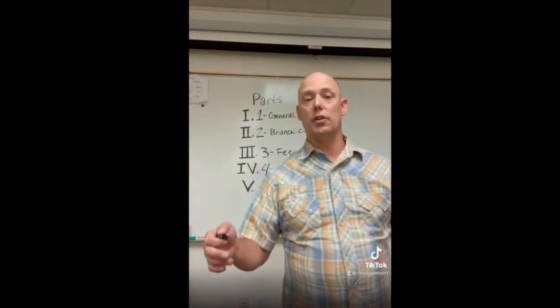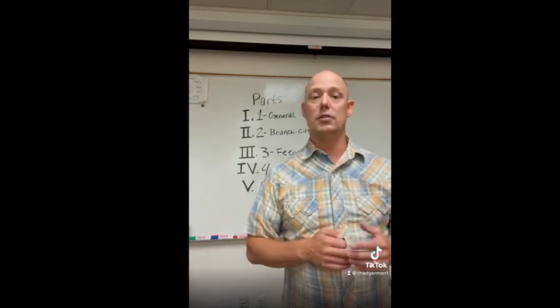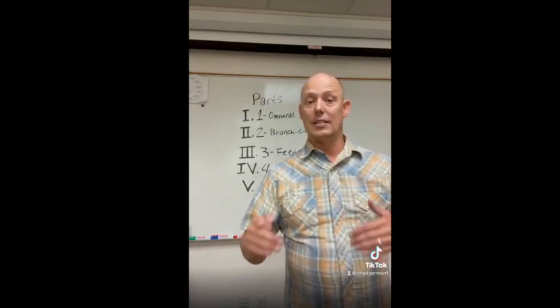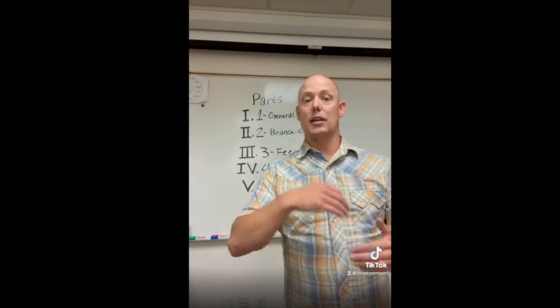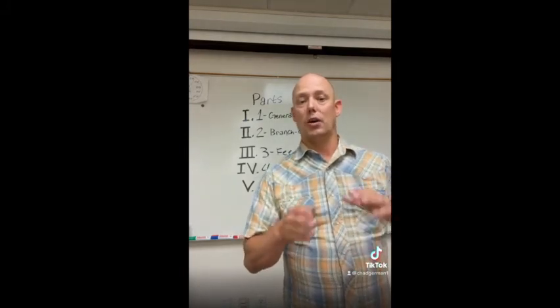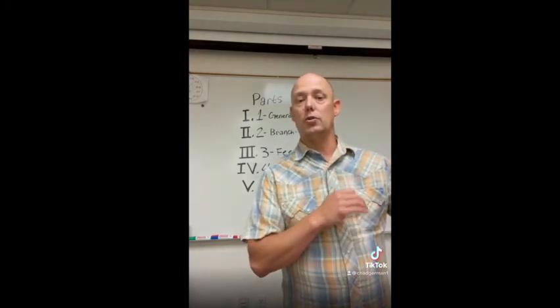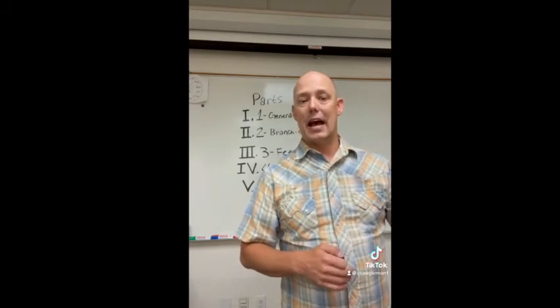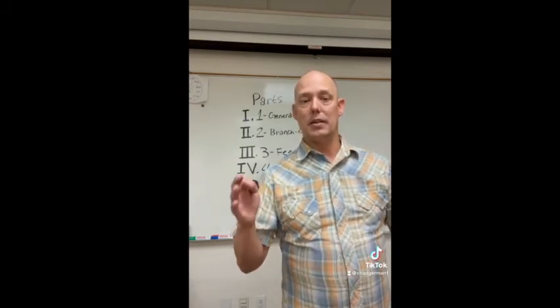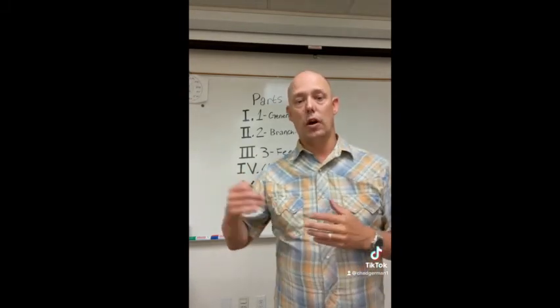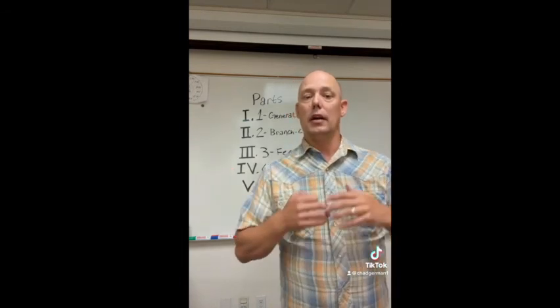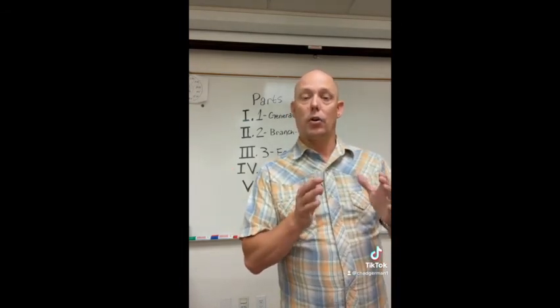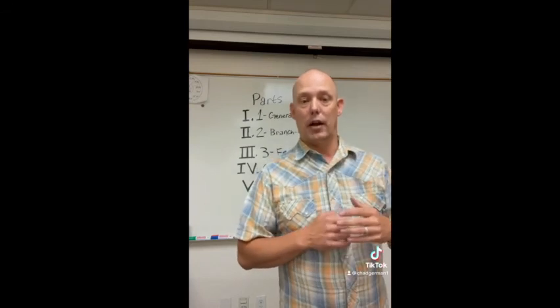Part 3 in 220.43 is talking about sizing the service. You're sizing a service that already has a show window, and it still says 200 volt-amps per linear foot. So they say the same thing and it seems like it's repeating itself, but it's not — you're talking about two different areas. One is adding a branch circuit and the other is sizing the service. Understand the parts, the article, and the chapter you're in.